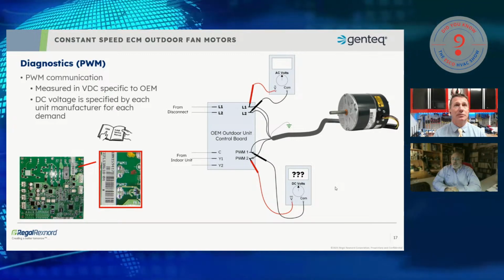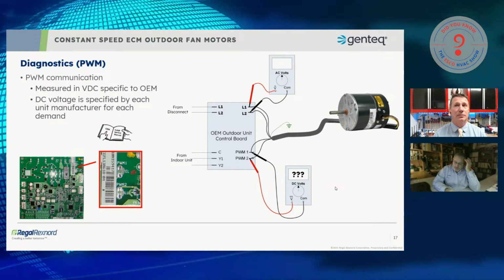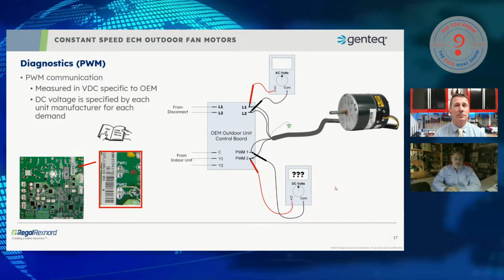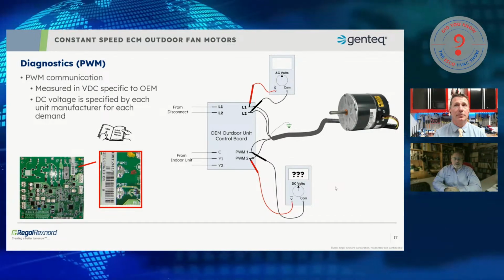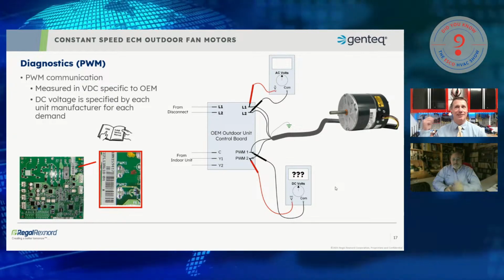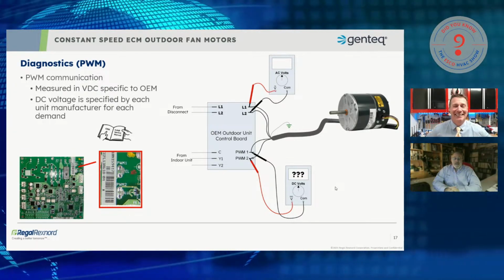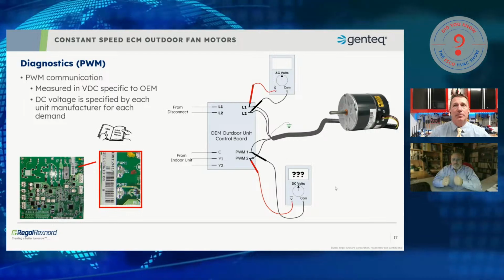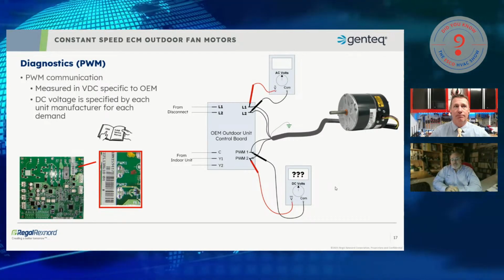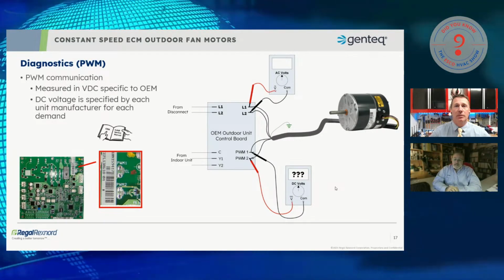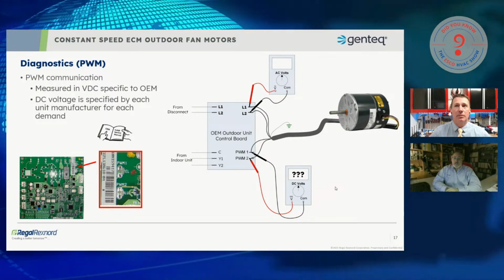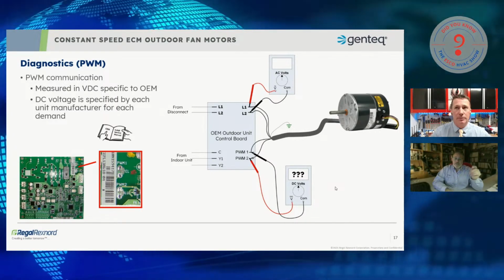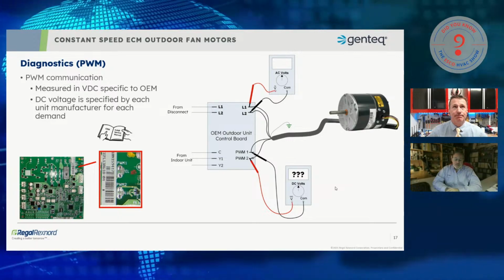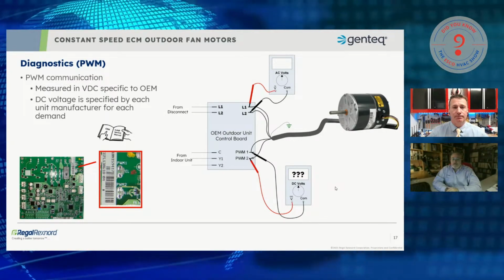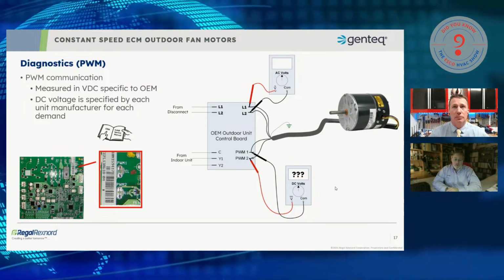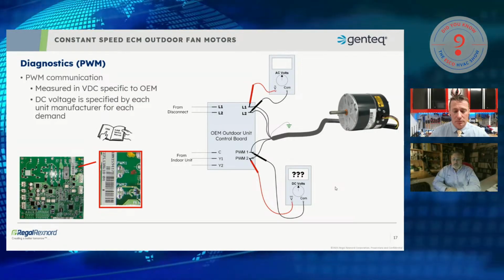Couple of challenges with that practice. One, if other technicians are like myself, where the only 9-volt battery on the truck is the one that's barely alive inside my voltmeter, that's going to be a challenge, because I will need a good 9-volt battery for it. There's also a certain amount of taping and wiring to get the right wires on the terminals. So I would say that that one manufacturer figured out that it worked on their motor because they knew how their engineers programmed it. I don't think it's going to apply very well to these outdoor fan motors, especially the ones that are in PWM. So I would suggest not using that trick on outdoor fan motors.